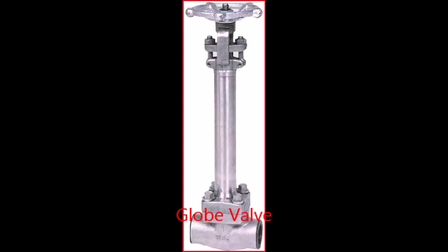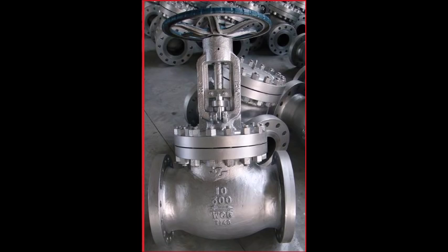The plug is also called a disc. In globe valves, the plug is connected to a stem which is operated by screw action using a hand wheel in manual valves. Typically, automated globe valves use smooth stems rather than threaded and are opened and closed by an actuator assembly.